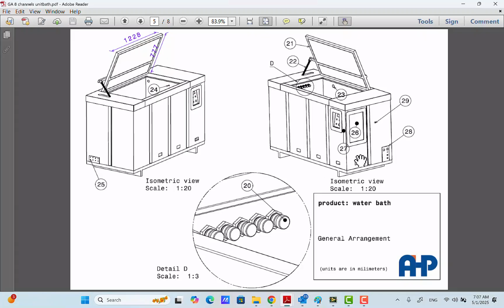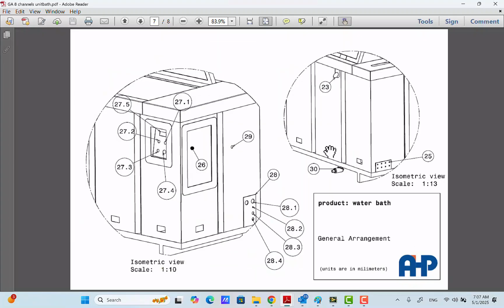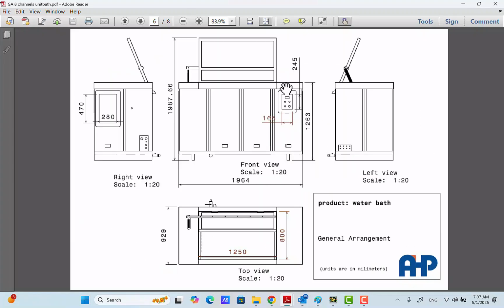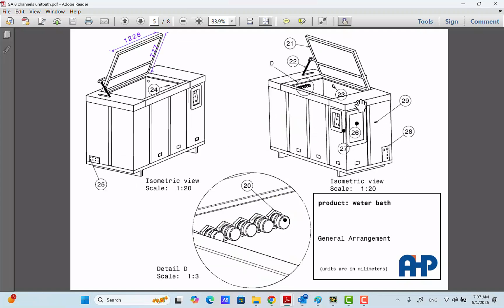Hot water bath with the heat exchanger inside it. I mean that is working with a chiller, has a heat exchanger inside it. On the right side of the water bath, inside it there is a small bath with a heating element inside it. Depending on the volume of the water, there are two, three, or one heating element. Each heating element has 6 kilowatts of power to raise the temperature inside the tank.